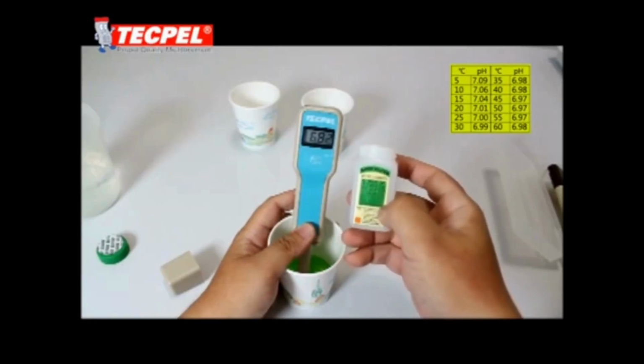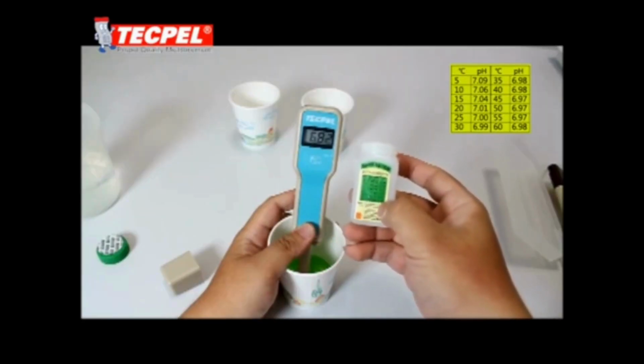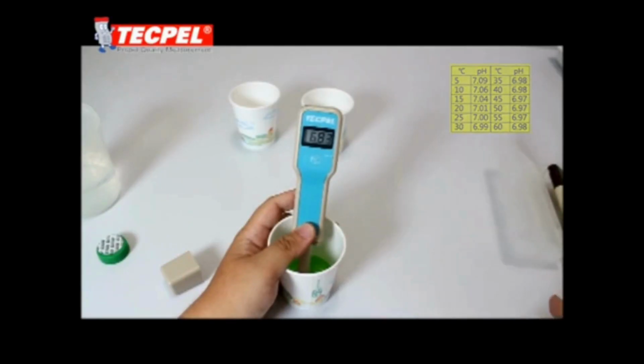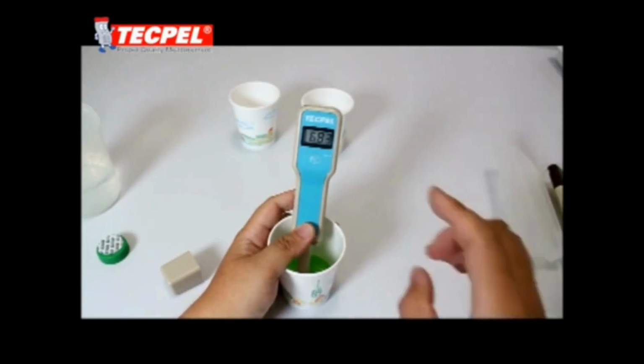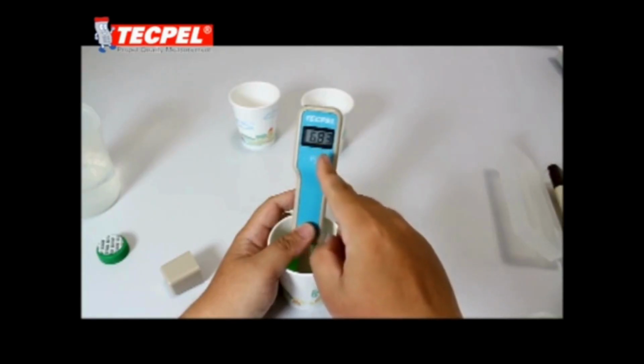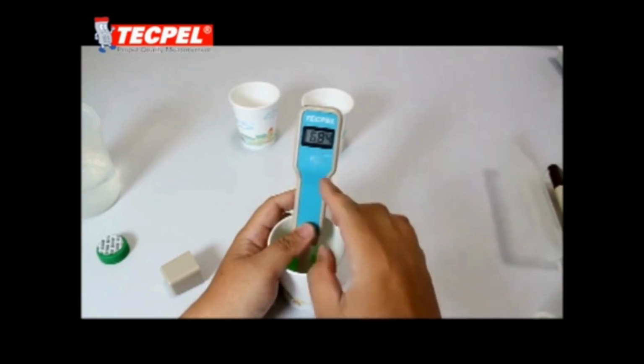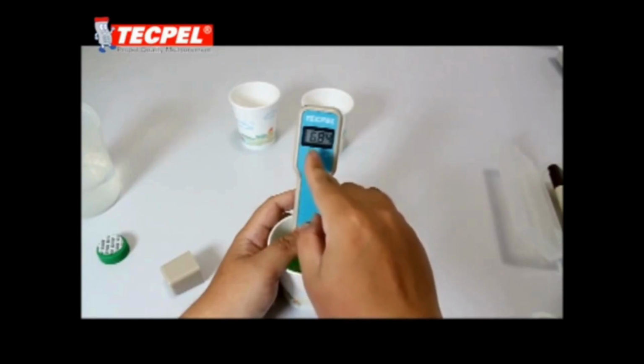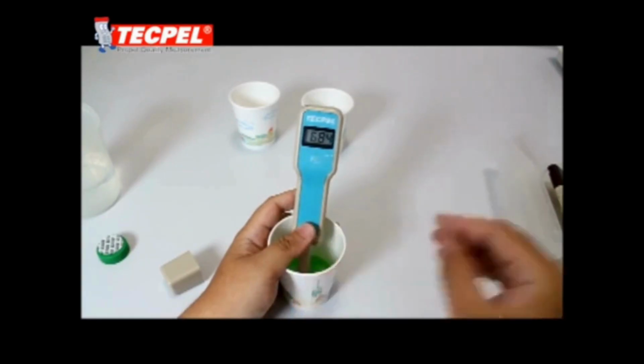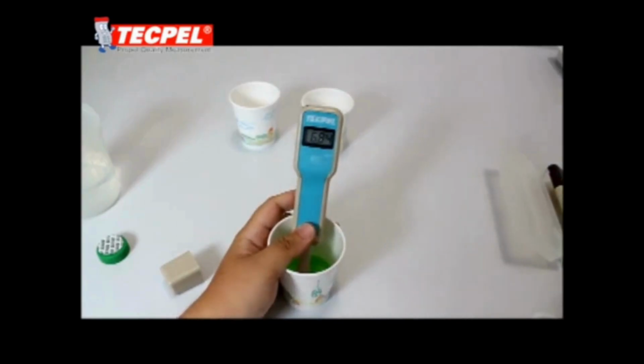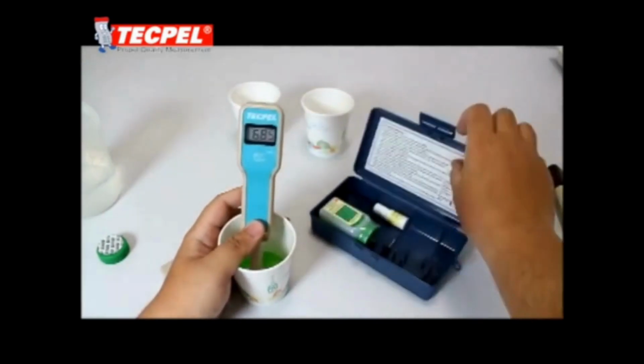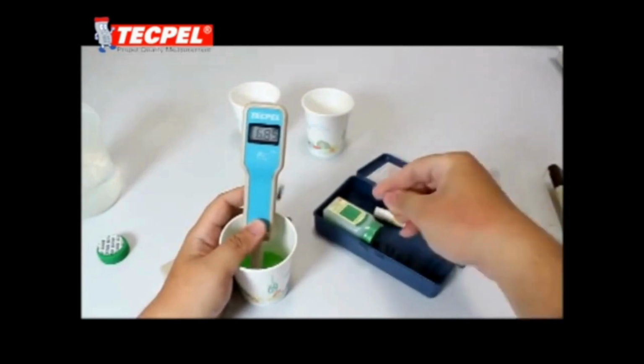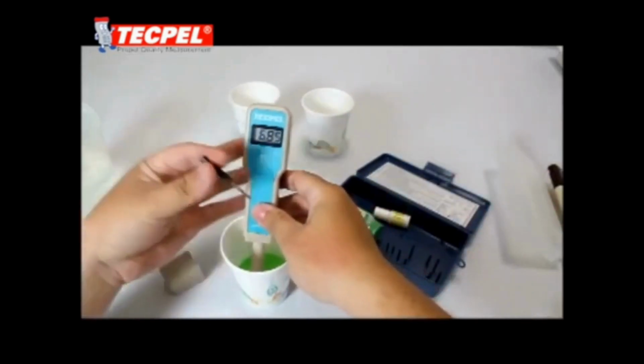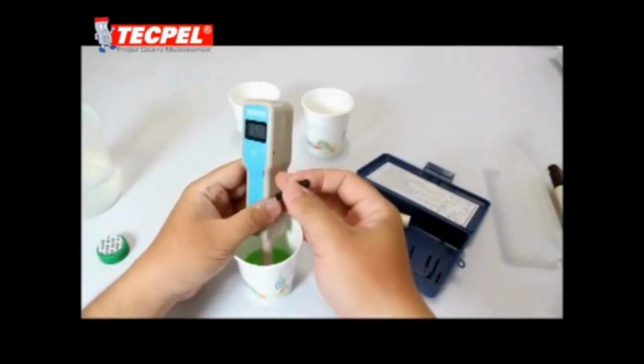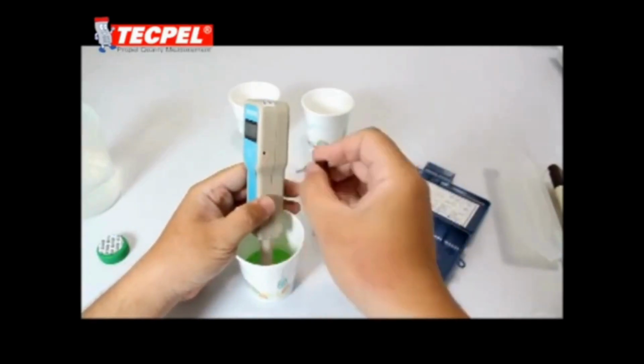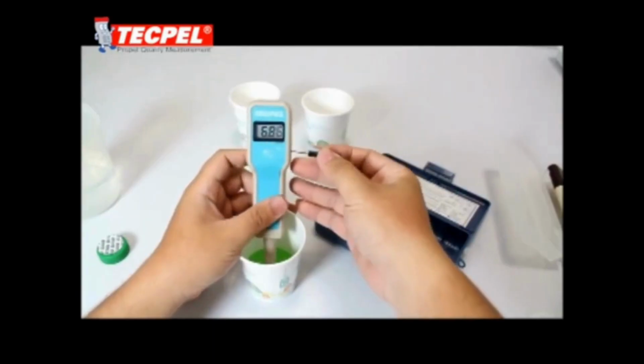If the reading does not show exactly 7.00, we can make a fine adjustment. For example, if the meter shows 6.84, we can adjust it to 7.00. Use the included small adjustment screwdriver and locate the calibration hole on the side of the meter. Insert the screwdriver gently and rotate it slowly while observing the display. When the screen shows exactly 7.00, the calibration process is complete. Now, remove the pH meter and rinse the sensor thoroughly with clean water. Once cleaned, the instrument is ready for real measurements.